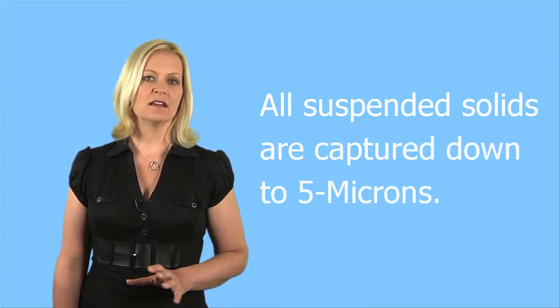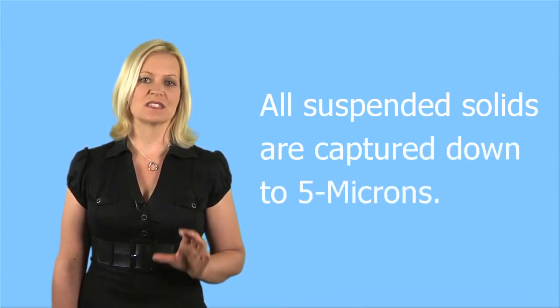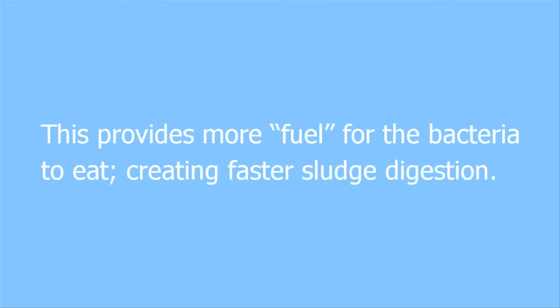When the recycler becomes saturated, which is determined by pressure, the global system automatically back-flushes the recycler, sending all of the captured suspended solids back to the aerobic digester. This provides more fuel for the bacteria to eat, creating faster sludge digestion.